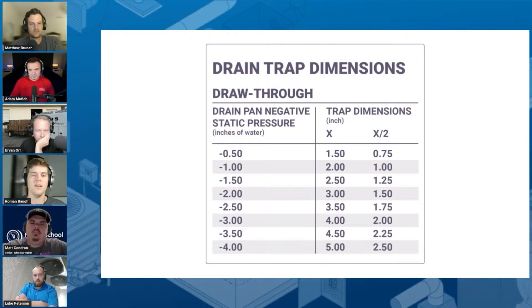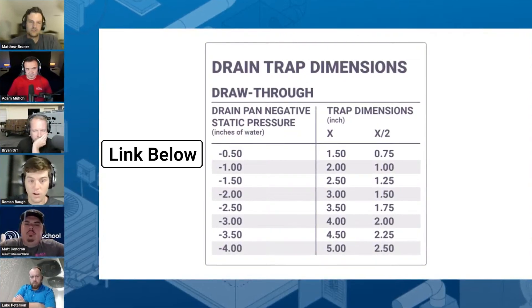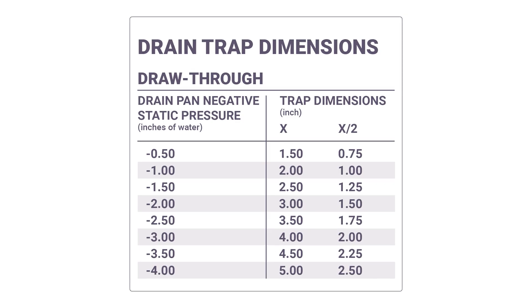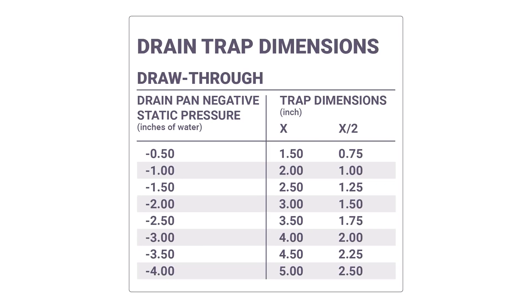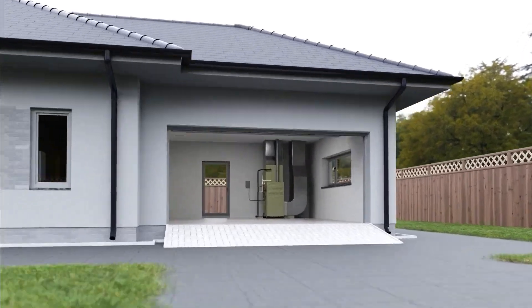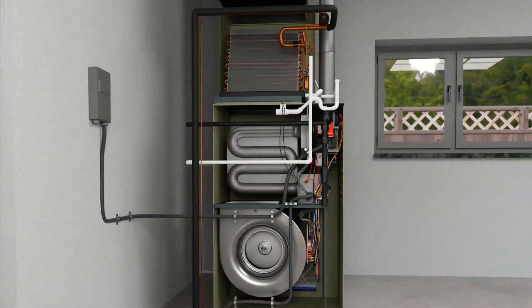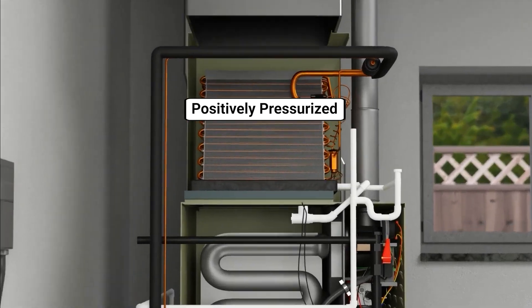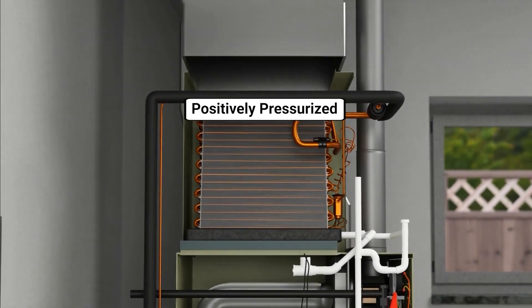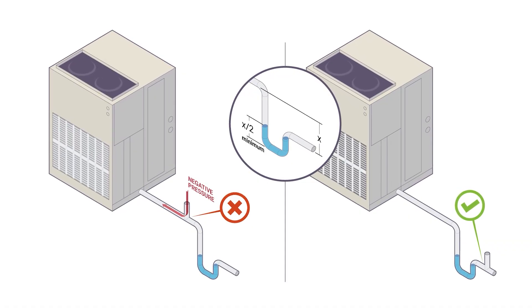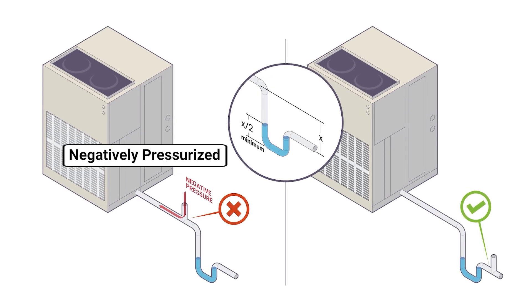Steven brings up a really good point — this idea of trap depth and its relationship to static pressure in negatively pressurized systems. To be clear, we're not talking about gas furnaces or systems where the evaporator coil is over the blower — those are positively pressurized and water wants to move out because the air is pushing it. We're talking about systems where we need to prevent air from pulling back into the drain line because it's negatively pressurized — typical for air handlers, pancake systems, and heat pumps where the evaporator coil is under the blower and therefore under negative pressure.